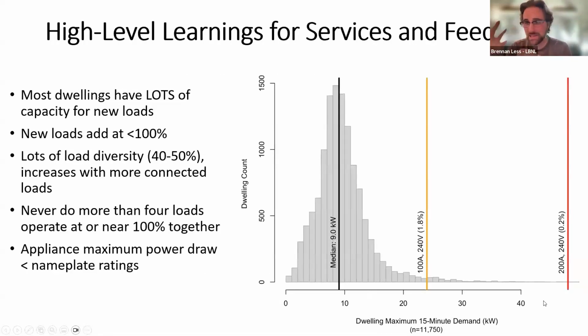High level learnings, just thinking about electrical service and feeders in homes. We found that most dwellings have lots of capacity for new loads. The plot on the right shows the distribution of peak demand for these homes that we have. Typically they use 9 kilowatts - that's less than half of a 100-amp panel, shown in that yellow line, and massively less than a 200-amp panel, shown in that red line. We see that almost no homes - like 98% of homes - use less than 100 amps, and 99.8% use less than 200 amps.